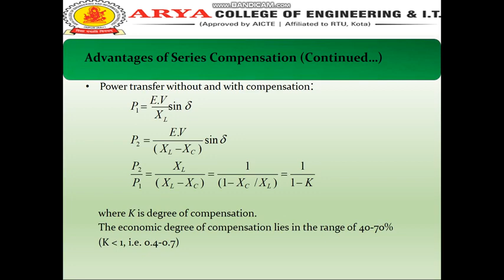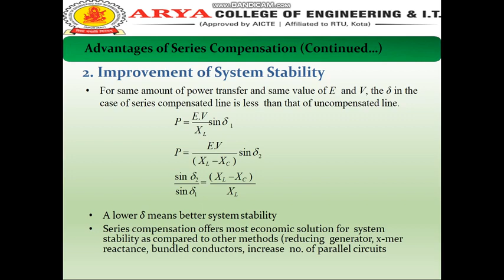The second advantage of series compensation is improvement of the system stability. For the same amount of power transfer and the same values of E and V, the delta in the case of a series compensated line is less than that of an uncompensated line. P equals EV upon XL sin delta 1 and P equals EV upon (XL minus XC) sin delta 2. Then it becomes sin delta 2 upon sin delta 1 equals (XL minus XC) upon XL. A lower value of delta means better system stability. Series compensation offers the most economical solution for system stability as compared to other methods.